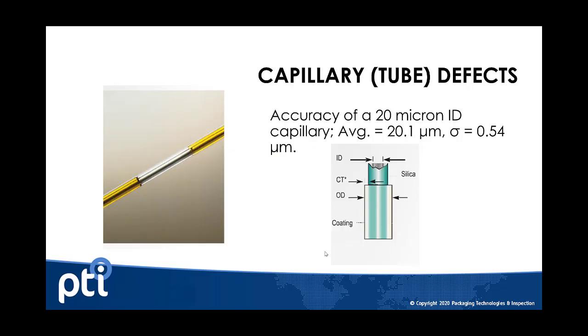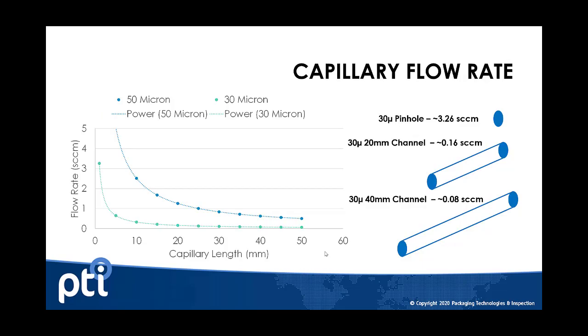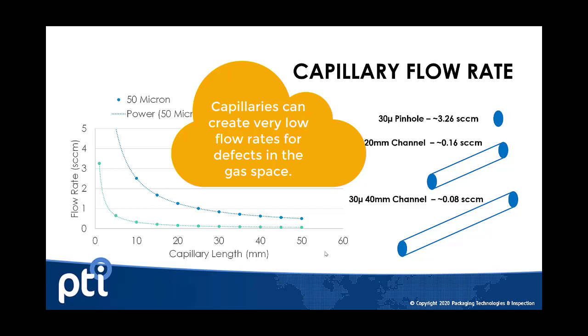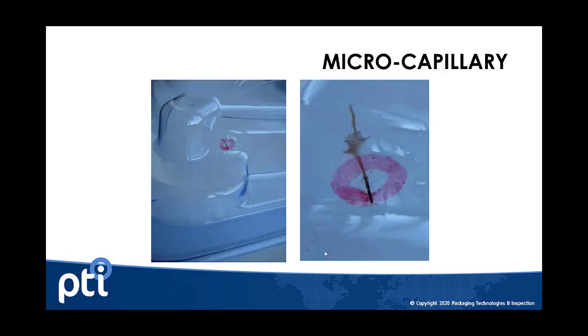You can also restrict the flow of gas using a capillary. A capillary is nothing more than a tube with a certified internal diameter. Based on the length of that capillary, you can create a restricted flow rate that is either greater or less. A capillary with an internal diameter of 30 microns can flow at a very small flow rate if elongated to 40 millimeters, or as great as 3.26 cc per minute if there's no depth to that defect. To use a capillary, you puncture a hole into the container, slide the capillary in, and glue it in place.